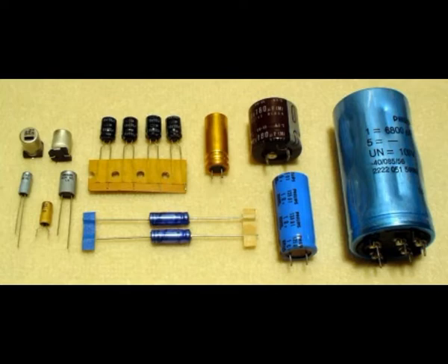Special bipolar capacitors designed for AC operation, usually referred to as bipolar, non-polarized, or NP types, are available. In these, the capacitors have two anode foils of opposite polarity connected in series. On each of the alternate halves of the AC cycle, one anode acts as a blocking dielectric, preventing reverse voltage from damaging the opposite anode. But these bipolar electrolytic capacitors are not adaptable for main AC applications instead of power capacitors with metallized polymer film or paper dielectric.